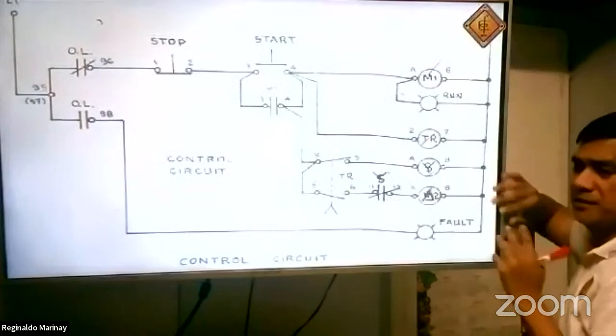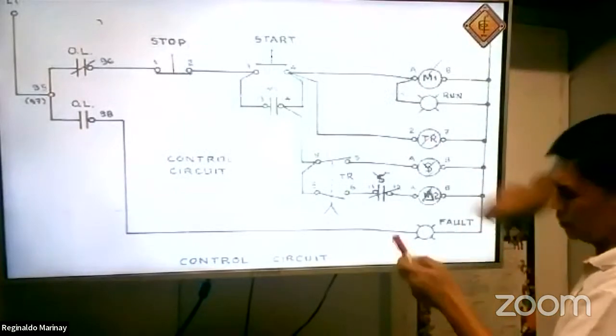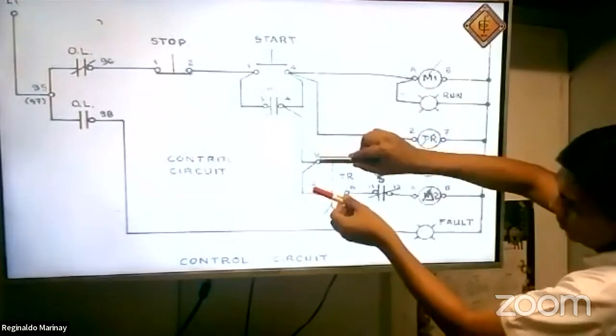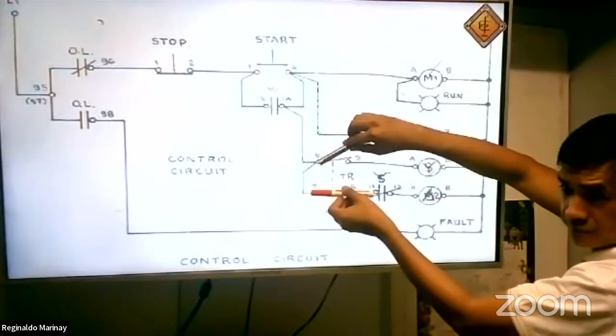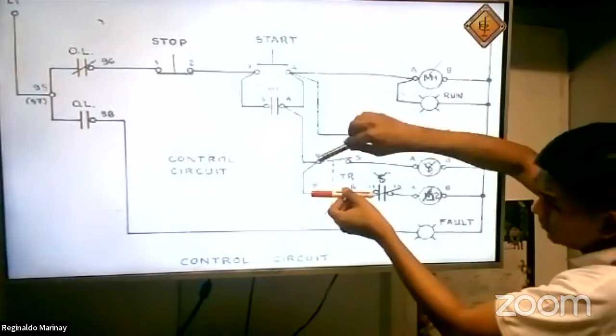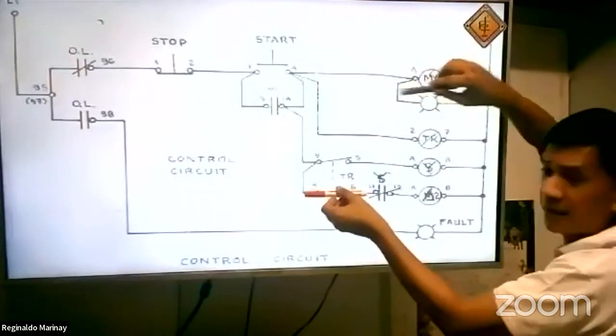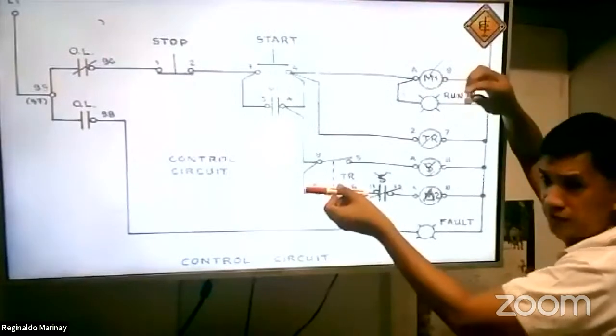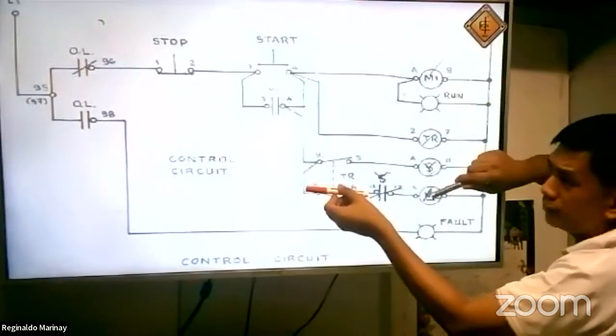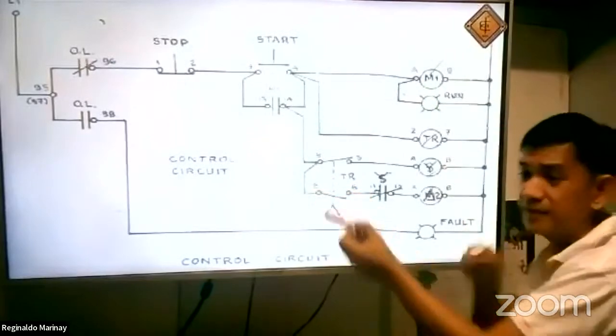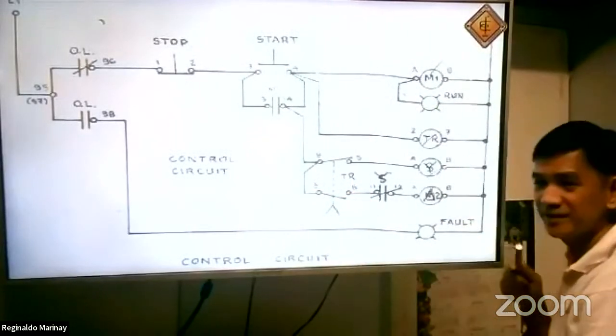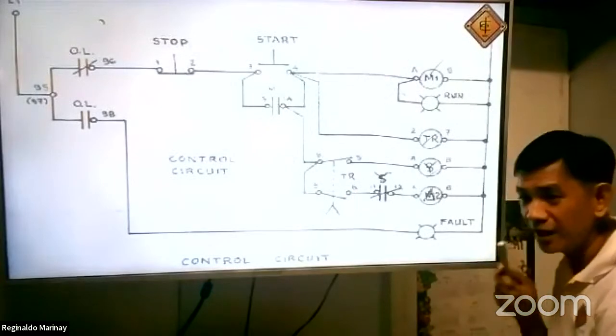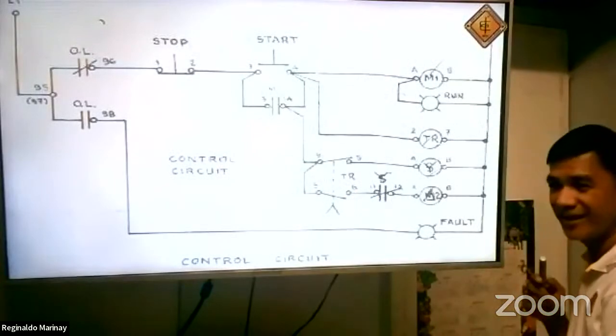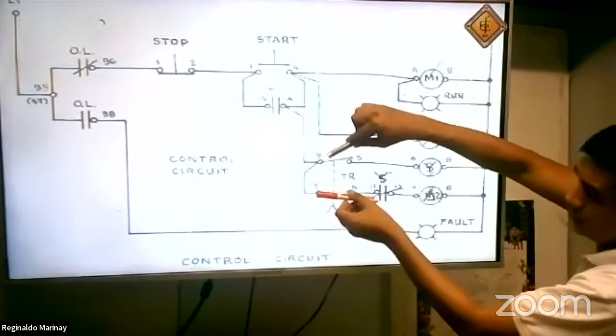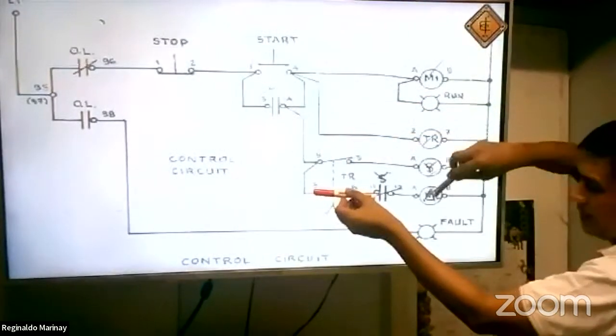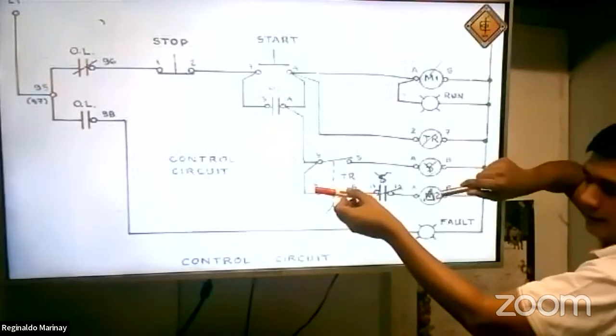I will count 3. Okay, 1, 2, 3. You see? This normally closed will become open, and this normally open will become closed, energizing your delta contactor. Now the Y contactor is being de-energized. Are you getting me? Can you follow? Okay, this opened, and this one is energized now. Remember, you energize the delta.